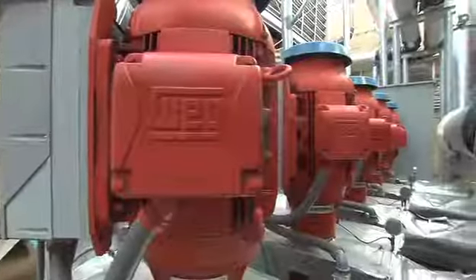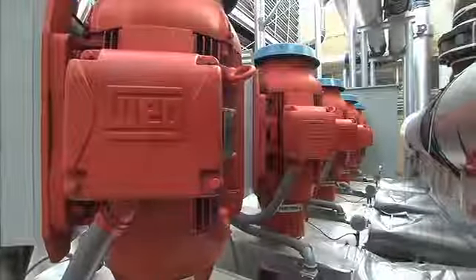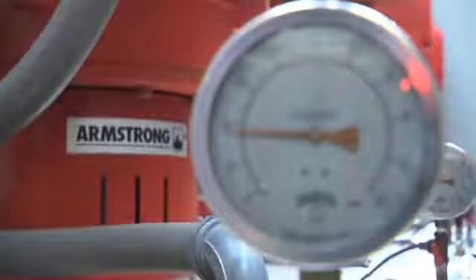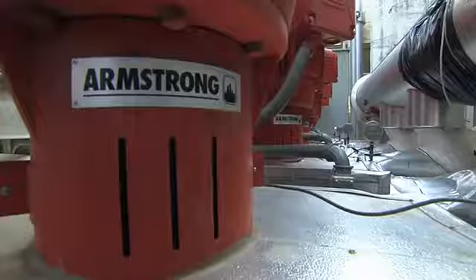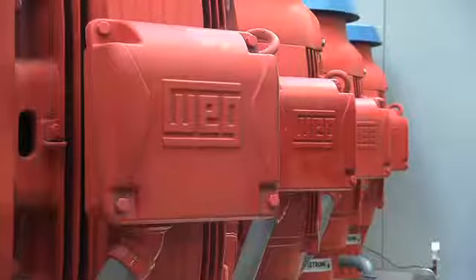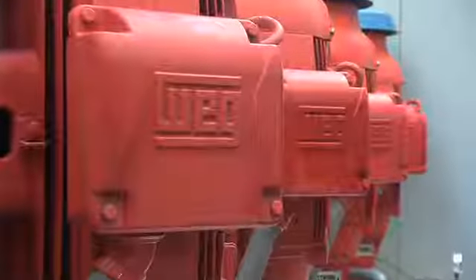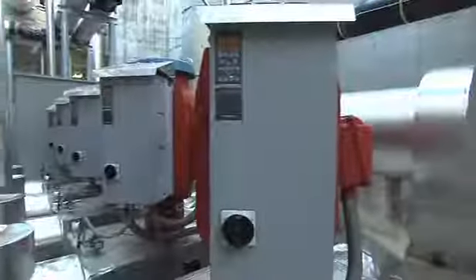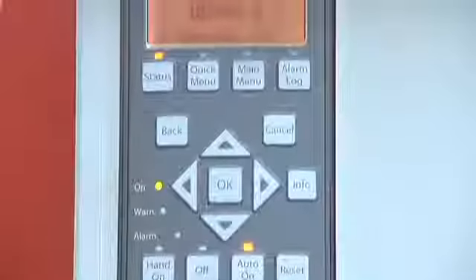Moving around to the other side of the cooling towers, we have the condenser pump station, designed and supplied by Armstrong Fluid Technology. The pump station consists of 5 design envelope Armstrong pumps, each 100 horsepower, so that there's 1 extra redundant pump for the cooling towers, as well as we provided the suction guide, Flo-Trex valves, and a common return header for the package. All of the electrical goes to a single point power connection, and all of the pumps receive their staging and speed signals from the Armstrong IPC controller.